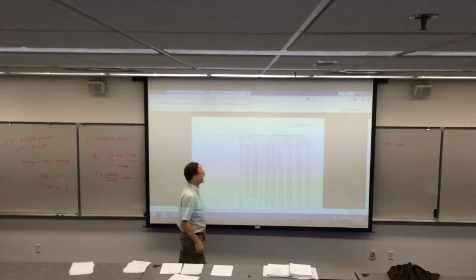Okay. So we figured out it was 0.107 ohms per 1,000 feet we're looking for. We want something less than that, and we want aluminum. So if I'm aluminum and less than 0.107, let's see, ohms per 1,000 feet.